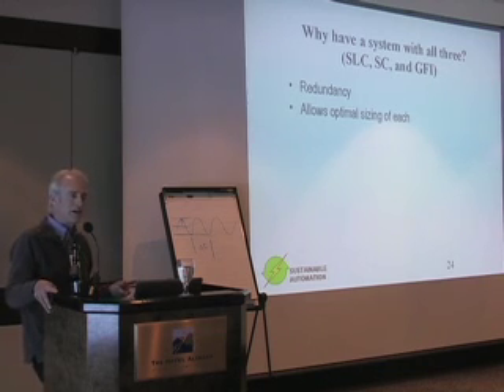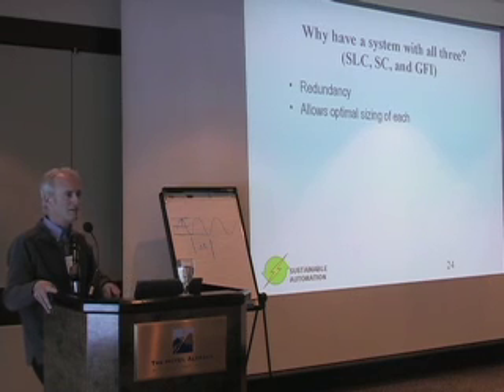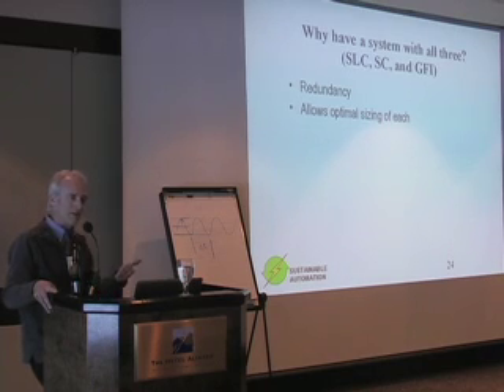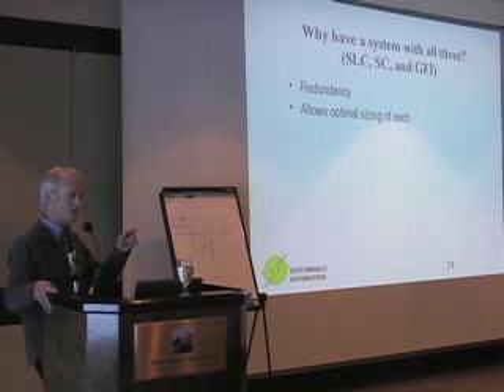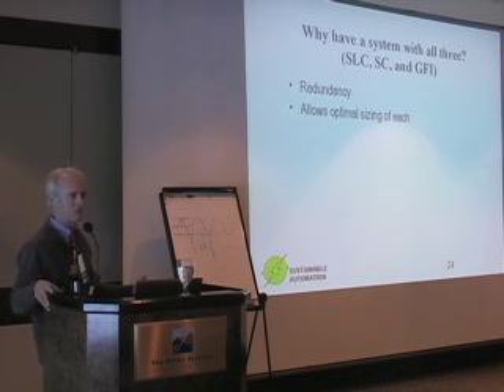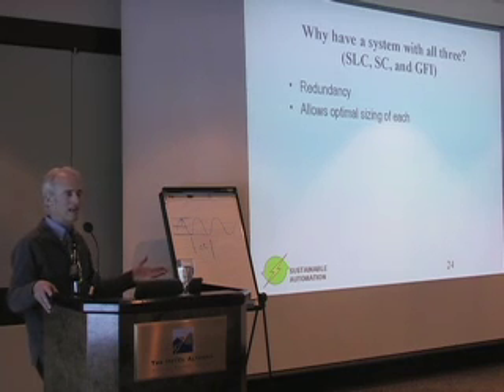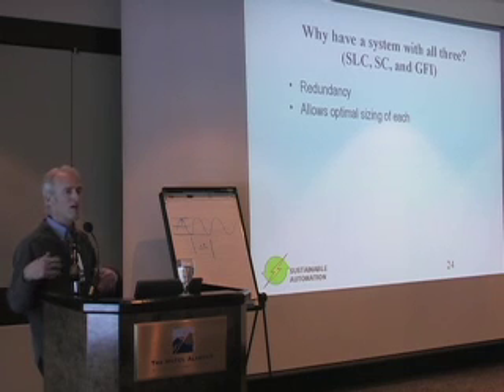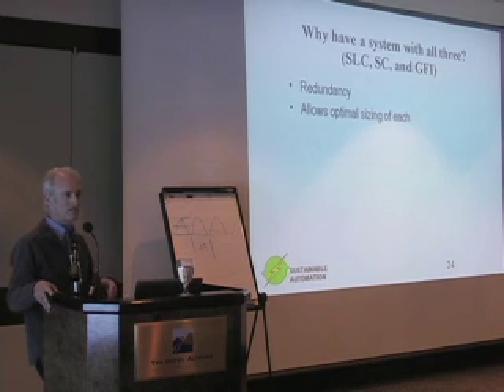Another reason is redundancy. We've got 3 solutions for frequency and voltage regulation. We've got the diesel generator. That's what it was designed to do. That's what it's been doing for years, all by itself. We've got the combination of the secondary load and synchronous condenser, which one of them controls frequency, one of them controls voltage. The 2 together can allow the system to operate in a fully regulated manner with the diesel shutdown, provided you have a margin of excess wind power. And then you have the inverter, which all by itself could control system voltage and frequency with the diesel shutdown. So the redundancy comes in between the inverter and the combination of the secondary load and synchronous condenser.